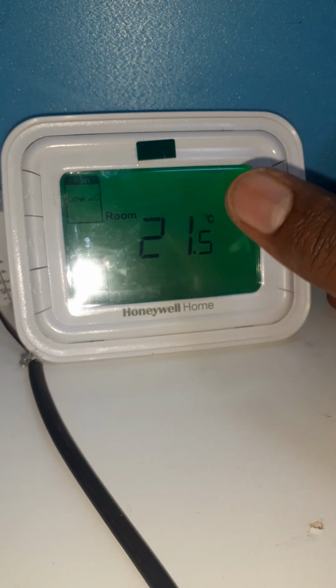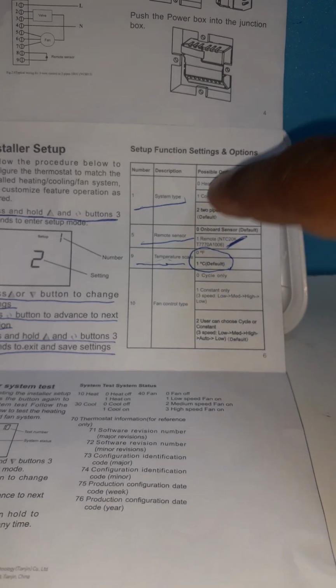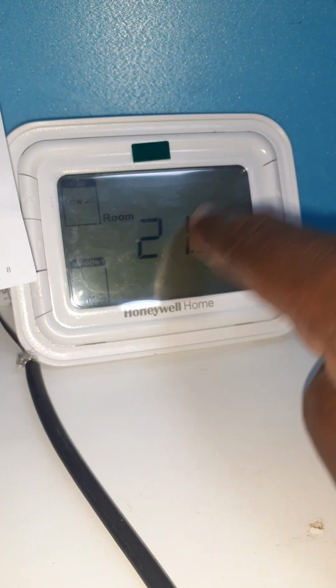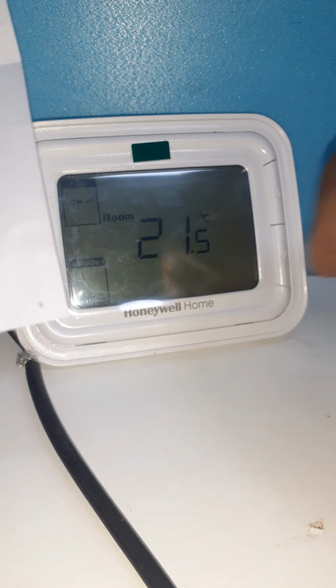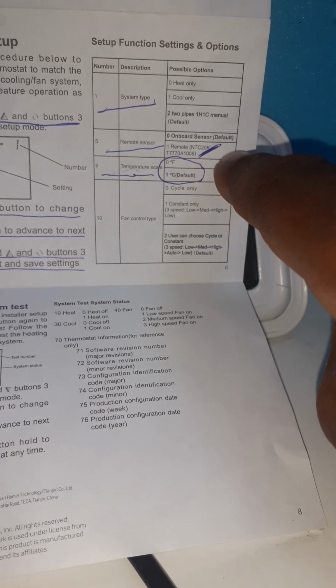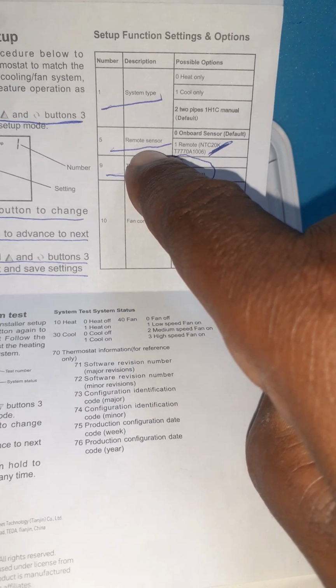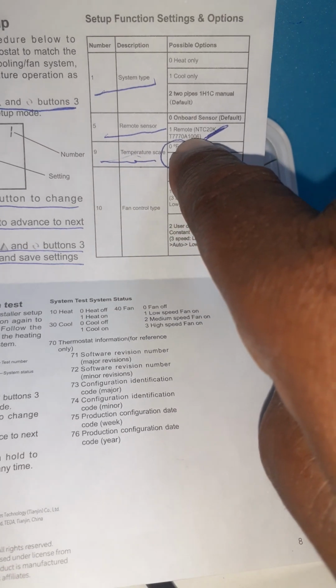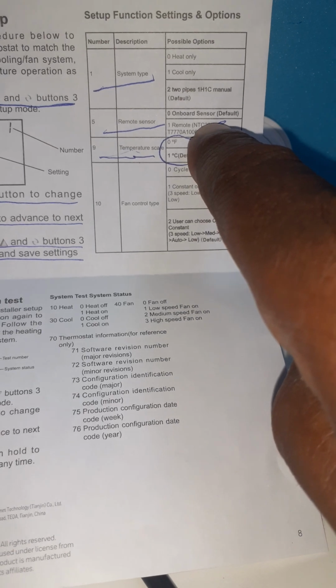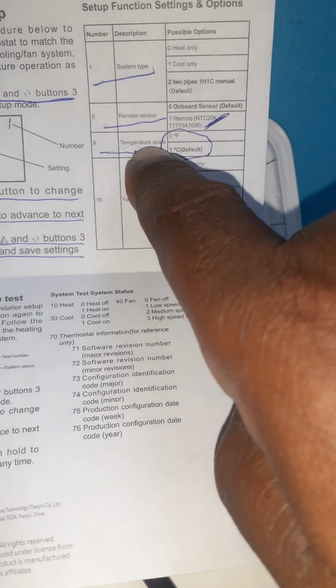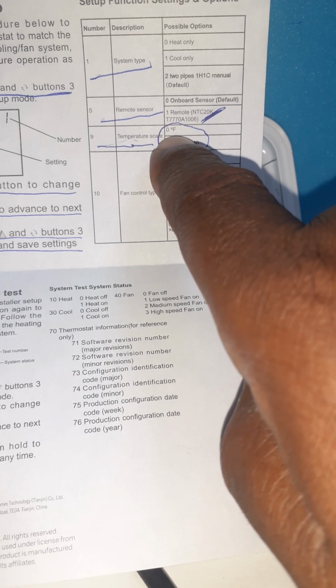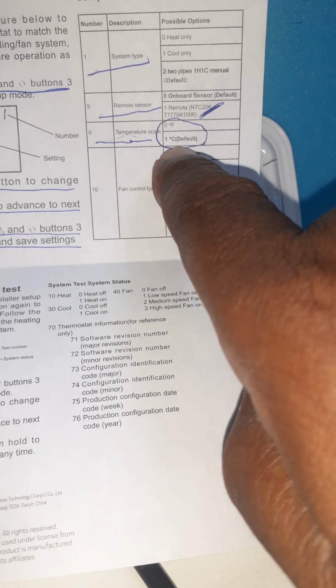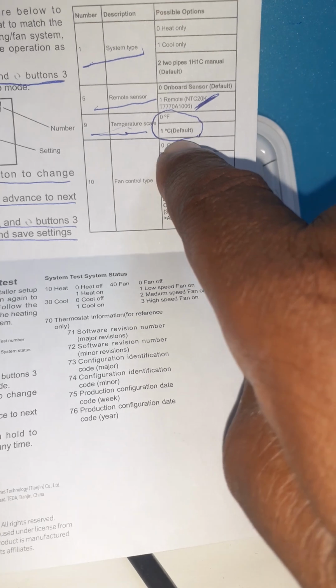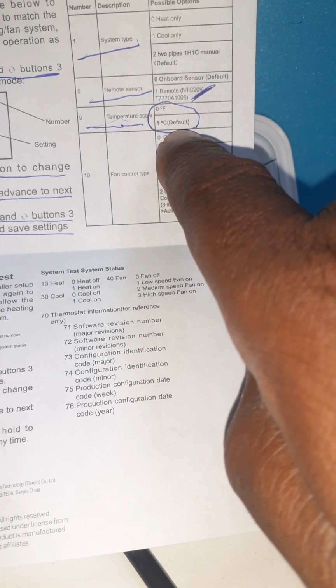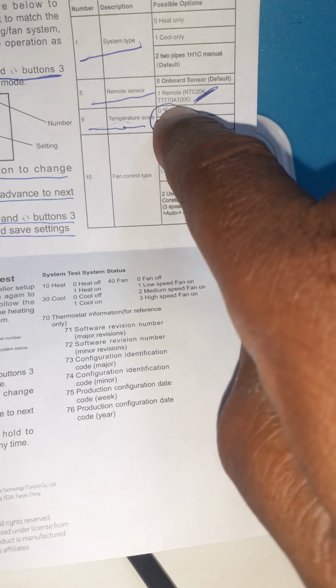Now I've set it at 2. What does 2 indicate here? At 2, our thermostat will work and set the temperature itself. Initially I had set remote sensor here at number 5, which you can see indicated. If I go to 9, I can set it to degrees Fahrenheit or degrees centigrade. In our case, the default is degrees centigrade, since we're dealing with centigrade, not Fahrenheit.